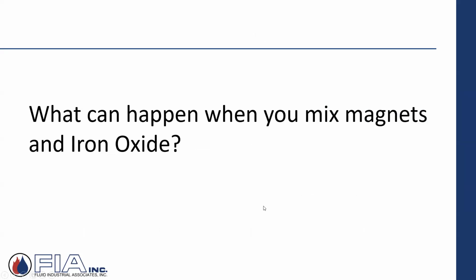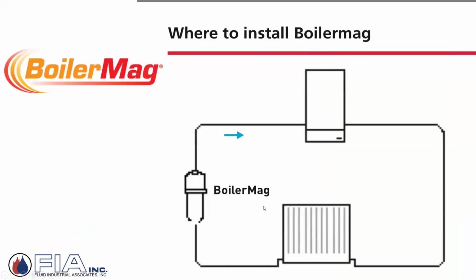One last thing, just to be aware of, you might have already heard of it. But as you adopt this technology, ECM, you're bringing these magnets in the pumps into your hydronic systems, which is all good. But over here on the East Coast, we have a lot of existing systems. If we're upgrading mechanical rooms, but we're attaching them to existing buildings, there's a chance that there might be some iron oxide, steel pipe, steel terminal units, iron oxide floating around in the system. Well, a magnet does a very good job of being a magnet. So if I have iron filings floating around, I need to protect my investment. My point is I'm leading up to some type of magnetic filtration.